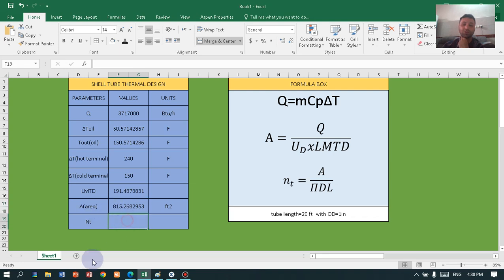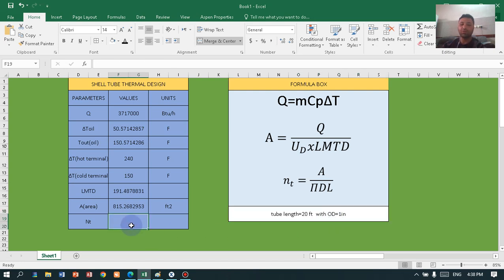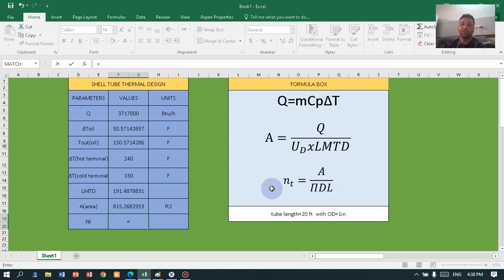For the number of tubes, we use the required area divided by pi times the internal diameter of the tubes — which is one inch — and the length of the tube, which is 20 feet. Make sure you convert the one-inch diameter into feet before entering the formula. Press equal, insert the area, and Excel will calculate the number of tubes.